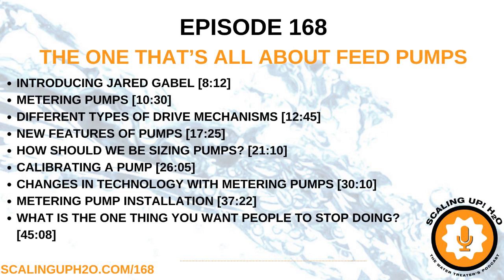In your opinion, what's been the biggest advantage to the metering pump when it first hit the market to the metering pump we have today? Metering pumps today are actually more than just a pump. They're able to see things around the system. They can detect system changes with sensors and all the smart technologies we put in it, like microcontrollers, the way we program them per pump to identify what the pump can actually feed as far as feed rate.